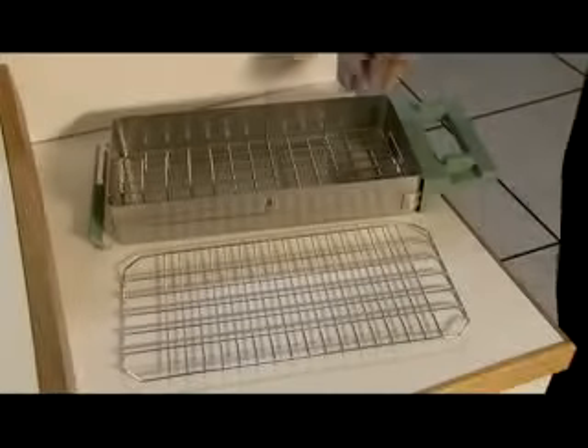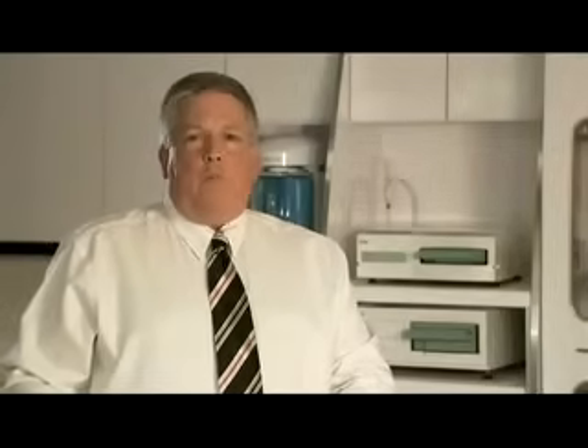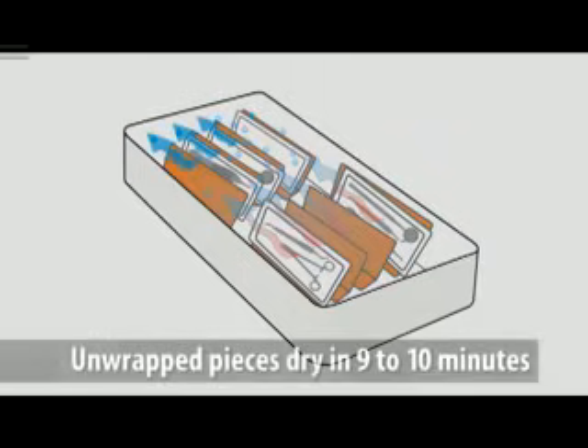There are two racks available in the Statim 5000. For both wrapped and unwrapped loads, place the rack feet-side down to maximize the flow of moisture out of the cassette. With the Radiant Heat System, vents take outside air and channel it through a biological filter and then into a hot boiler. The hot air circulates inside and dries the load. Unwrapped pieces dry in only 9 to 10 minutes.